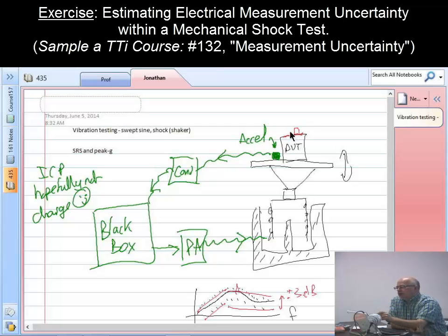I forget why they had the accel on the top, because they had, I forget, 2 or 3 accels on the head as well. But so the control one was put on top of the DUT for some reason in this case. I mean, a lot of times people will want to put it as far away from the shaker, just because that'll be the highest environment, so... No, they didn't really have a very good reason.